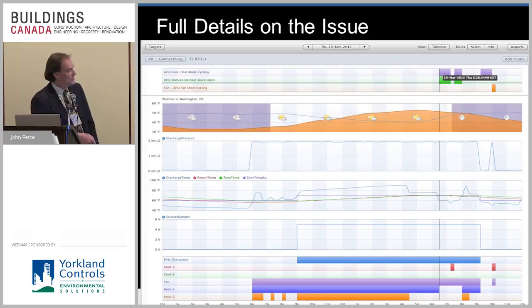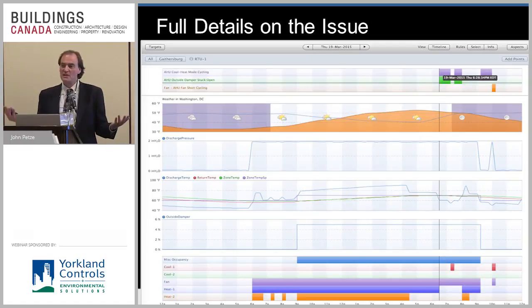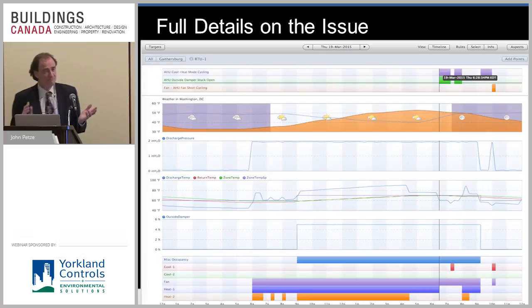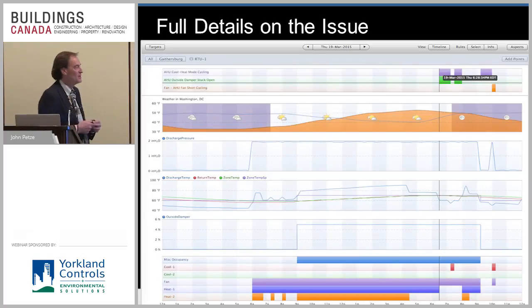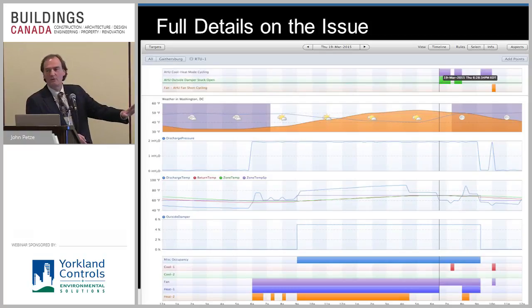It didn't get checked out, commissioned, or found, or maybe it's a seasonal thing, but we've been hitting demand peaks. What if I have 200 zones and this is happening everywhere with electric reheat? Chasing that down manually? Absolutely possible. Practical? Viable? I would suggest no. But the point is we're seeing patterns even though we didn't write a rule to look for it, because this whole idea is converting data into information and patterns for people to consume.